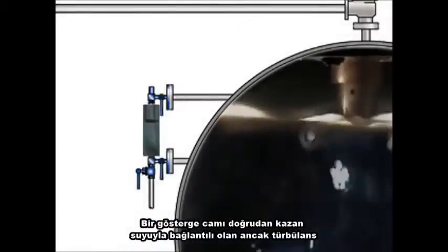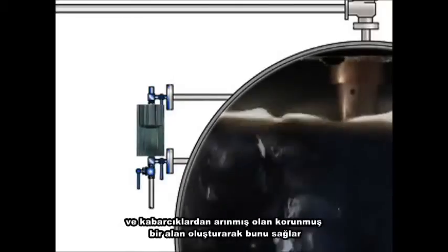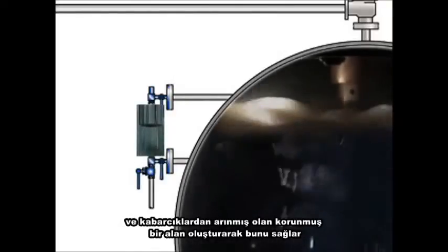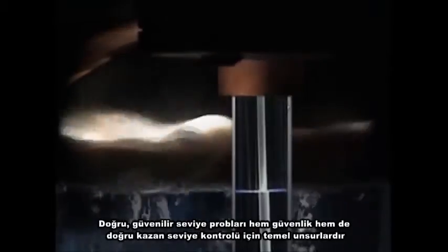Level gauges aim to measure the level of the top of the boiling water, just below the bubble layer, where the water-to-bubble ratio is fairly representative of much of the boiler, and this is the level you see in the gauge glass. A gauge glass achieves this by providing a protected zone directly connected to the main boiler water, but free from turbulence and bubbles. Similarly, level probes installed inside the boiler must be in protection tubes. Accurate, reliable level probes are essential for both safety and precise boiler level control.